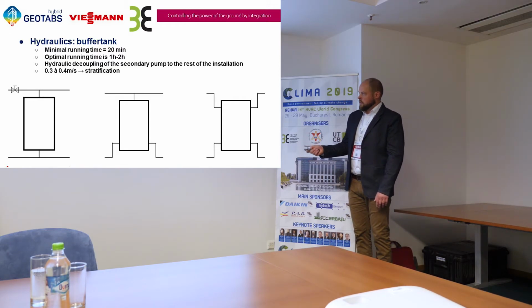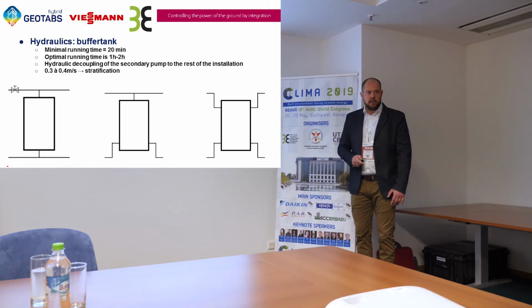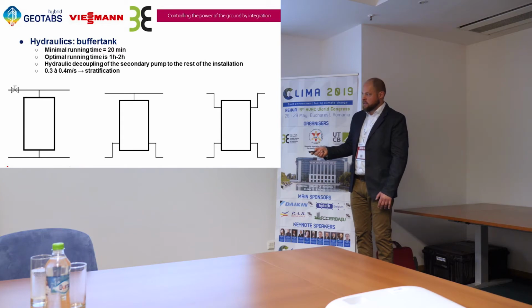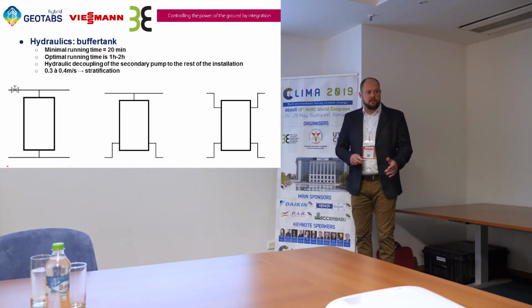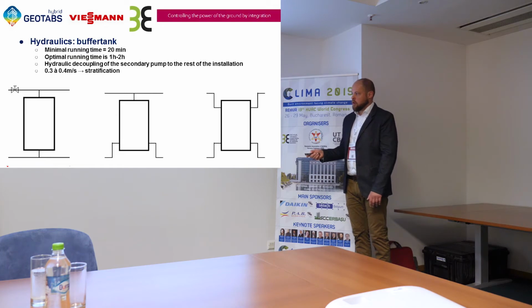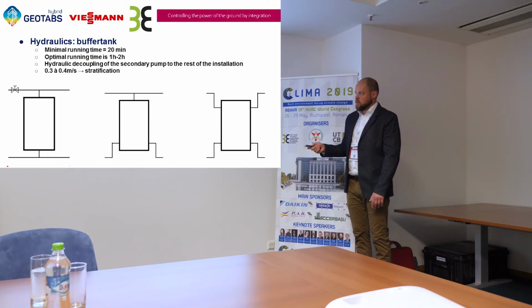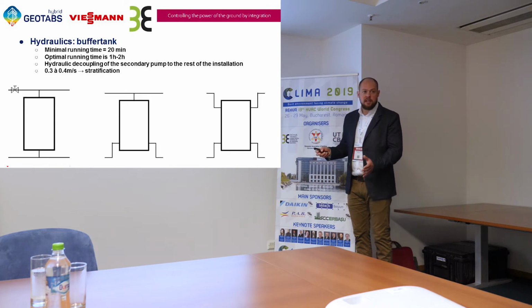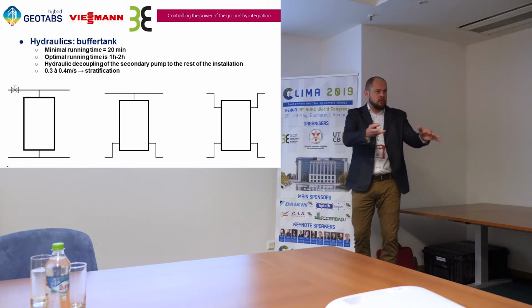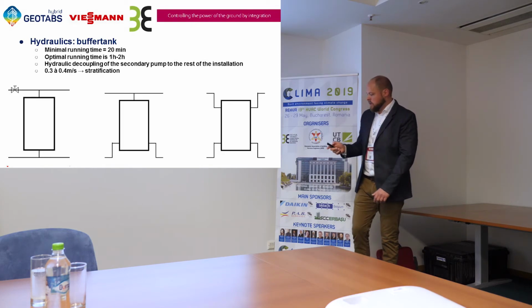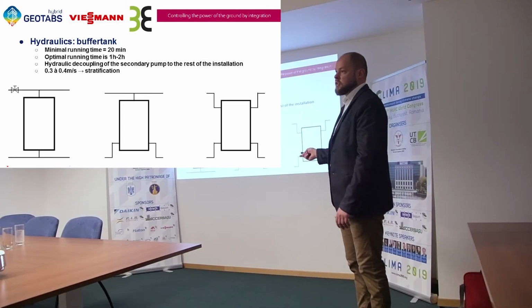This is one of the schematics we use today in the larger applications. So the heat produced by the heat pump is immediately transferred to the installation. Only the excess flow is put through the buffer tank. And then you can ask, why not do it like this? This can give some problems. When the pressure drop over this side is lower than through the buffer tank, sometimes that can be, this is a schematic, but we have a lot of turns and things, that can be a problem. Then we see that the buffer isn't discharged.